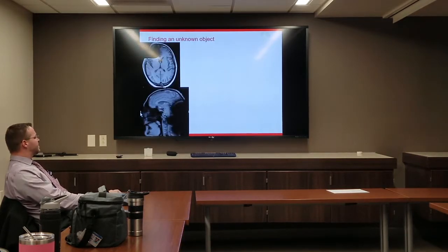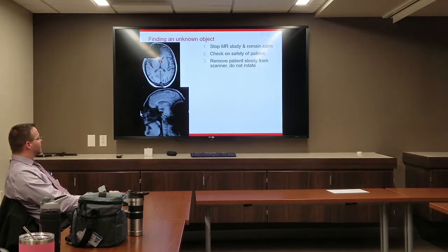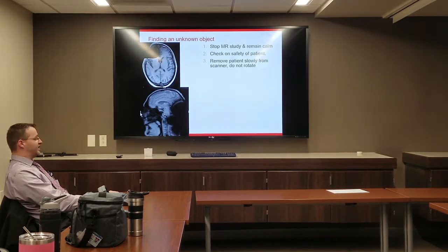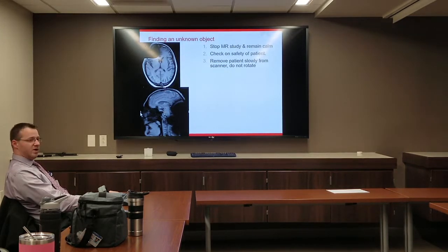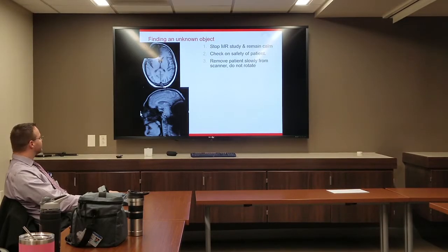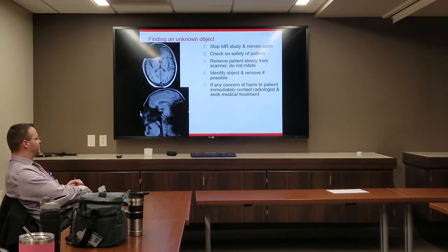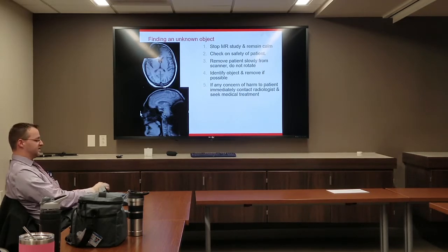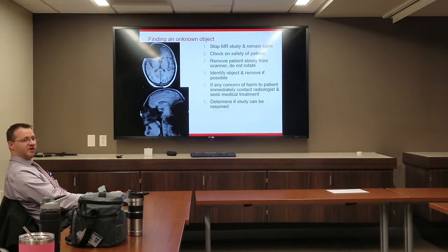For finding unknown objects during a scan: stop the MR study, remain calm, and check on the patient's safety. Remove the patient slowly from the scanner — do not rotate or have them move until they're clear and far away from the magnet, as rotating the table could cause an object to torque in the body and cause harm. Bring the table straight out as far as possible before turning. If you can identify the object, remove it if possible. If there's any concern of harm, contact your radiologist and seek medical treatment. Then determine if the study can be resumed.